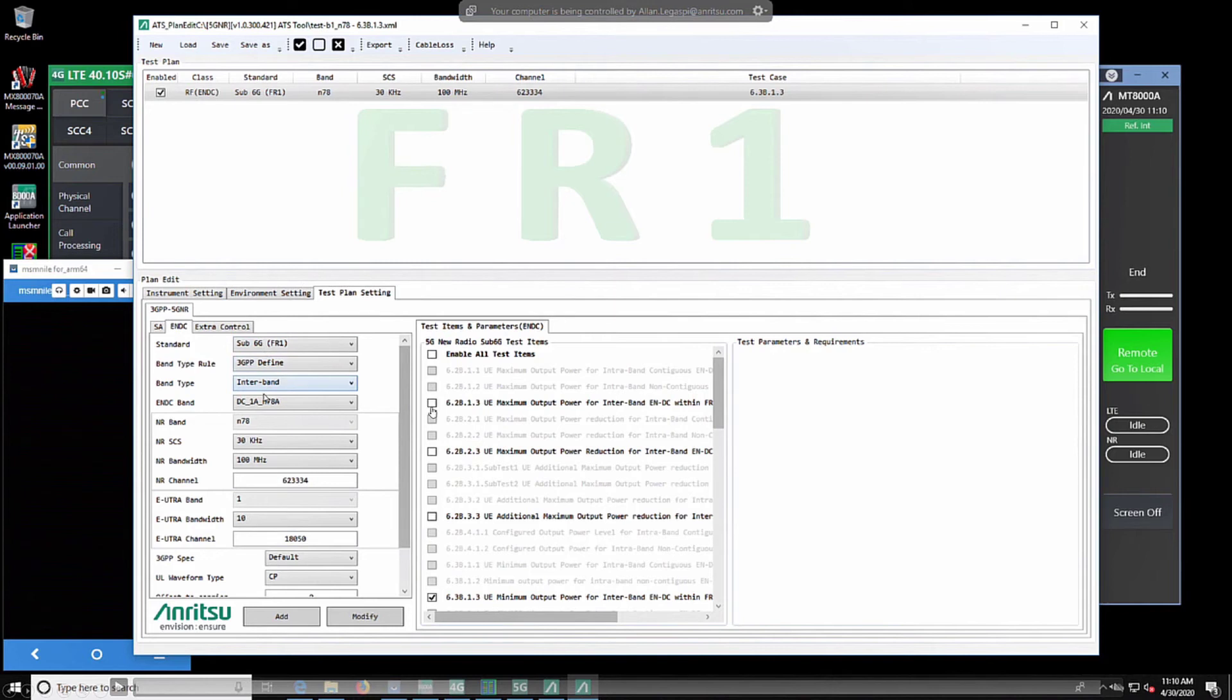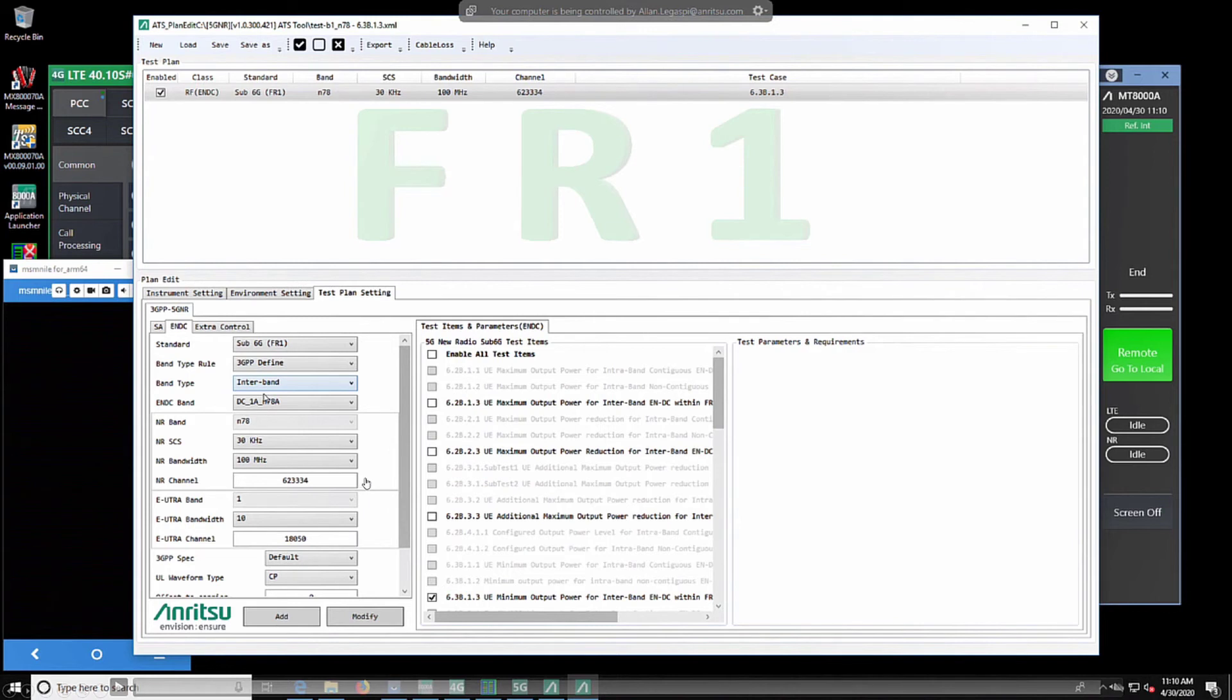Here we have our test plan settings where we would set our LTE or NR bands, 5G bands, we would set our subcarrier spacing, we would set our channels, and our bandwidth. Please remember that this is based on 3GPP spec where all of our channels are predefined.